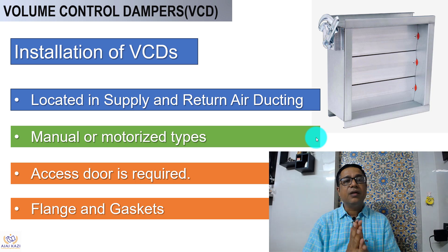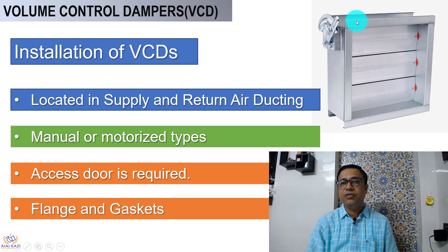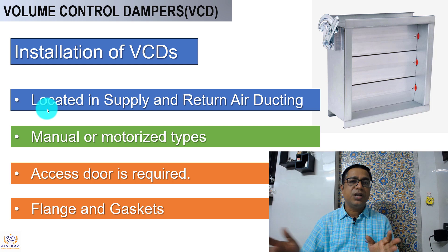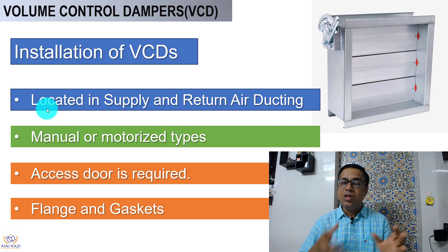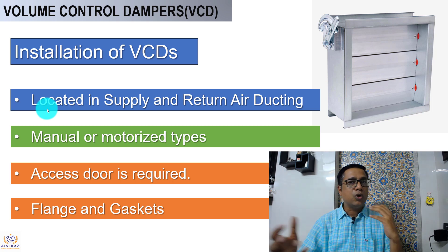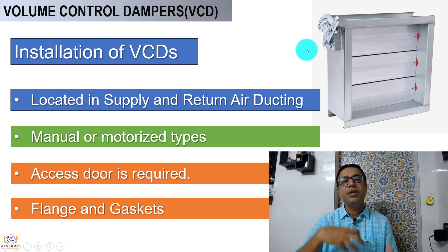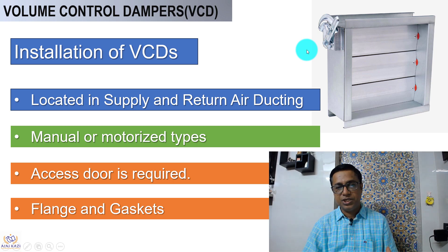Now let us look at the installation of VCDs. This is a VCD — you can see the handle, and this is a multiple blade damper. Generally, VCDs are located in supply or return air ducting. VCDs come in two types: manual, like this one, and motorized.